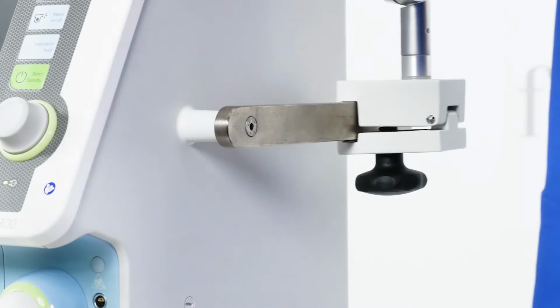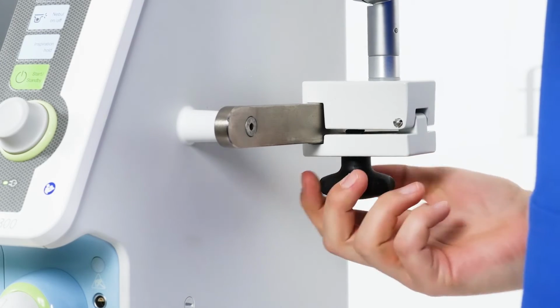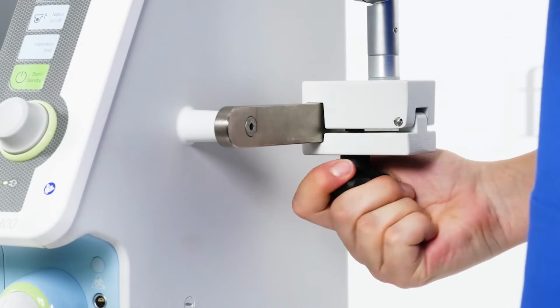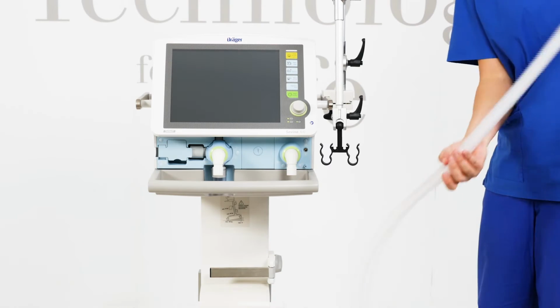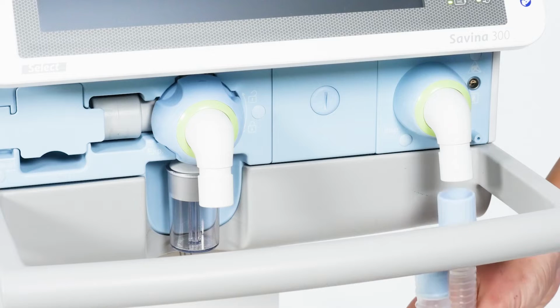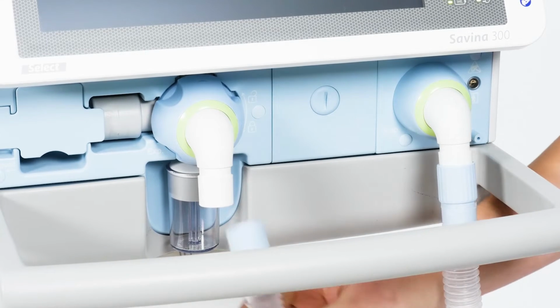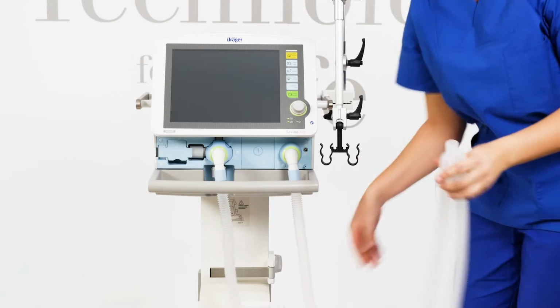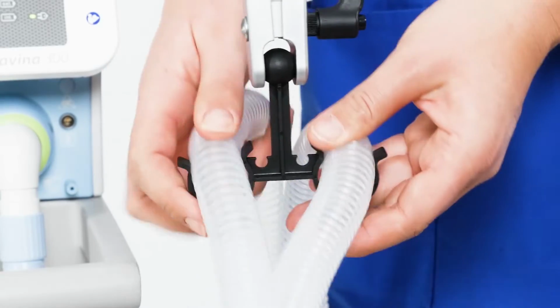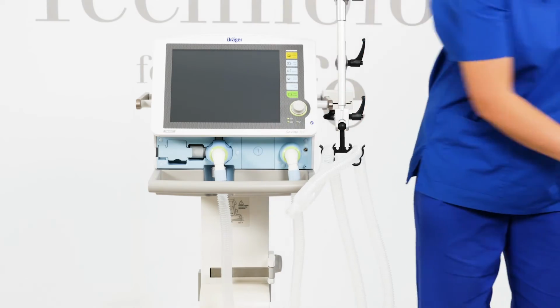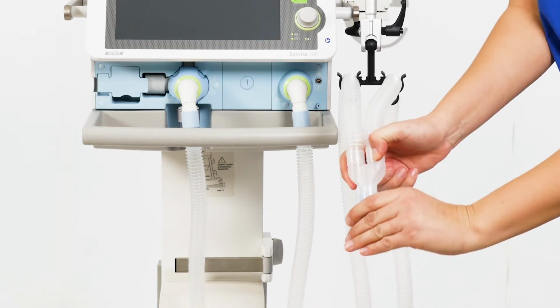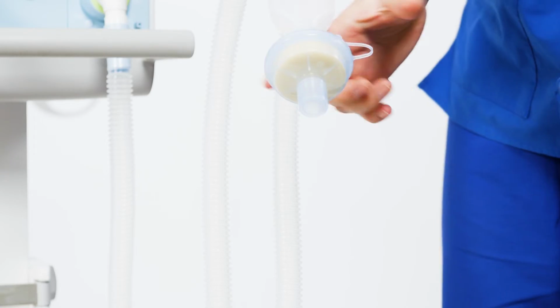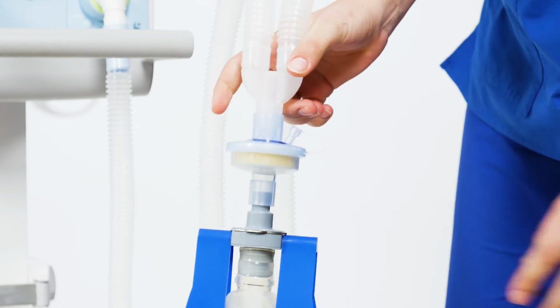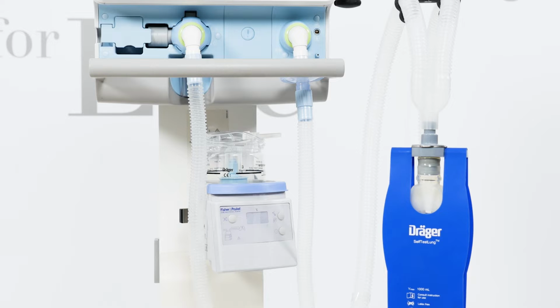Hang the hinged arm on the lateral standard rail of Savina 300 Select and tighten the screws. Connect the breathing hoses to the inspiratory port and to the expiratory port. Insert the breathing hoses in the opening of the hinged arm. Then the filter, HME, on the Y-piece, and the test lung on the HME. If no HME is used, a breathing gas humidifier should be installed on the humidifier holder.